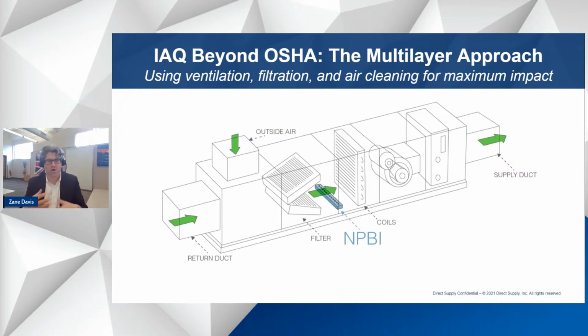With air quality, you very much need a multi-layer approach, especially for pathogen control and reducing exposure to pathogens and the risk of infection. You need to add all of these layers on top of each other to reduce the risk as much as possible. The OSHA standard talks about maximizing air changes per hour and getting as much outside air into the system as possible. You can see filters in this diagram, making sure you're getting to the highest MERV rating your system will allow. We also have technologies like needlepoint bipolar ionization that actively fight pathogens in your system without increasing static pressure or wear and tear.